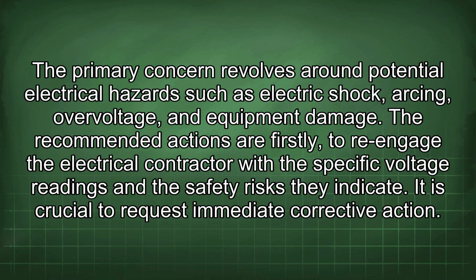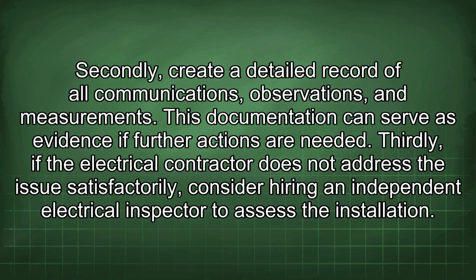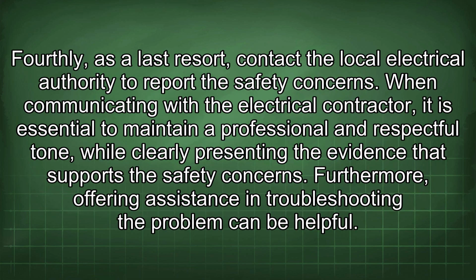The recommended actions are, firstly, to re-engage the electrical contractor with the specific voltage readings and the safety risks they indicate. It is crucial to request immediate corrective action. Secondly, create a detailed record of all communications, observations, and measurements. This documentation can serve as evidence if further actions are needed. Thirdly, if the electrical contractor does not address the issue satisfactorily, consider hiring an independent electrical inspector to assess the installation. Fourthly, as a last resort, contact the local electrical authority to report the safety concerns.